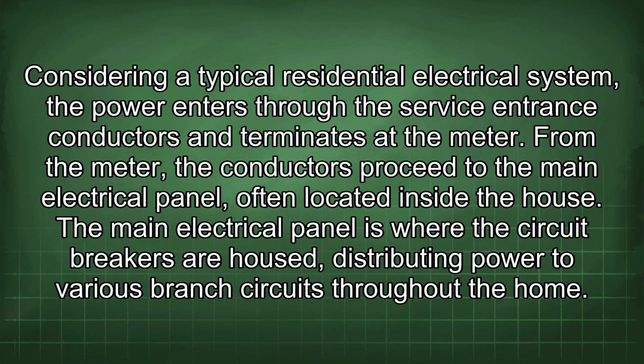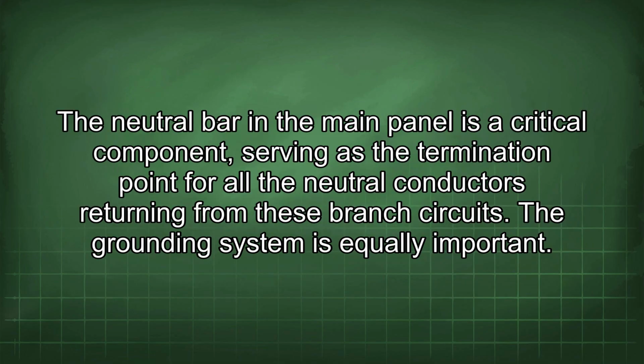Considering a typical residential electrical system, the power enters through the service entrance conductors and terminates at the meter. From the meter, the conductors proceed to the main electrical panel, often located inside the house. The main electrical panel is where the circuit breakers are housed, distributing power to various branch circuits throughout the home. The neutral bar in the main panel is a critical component, serving as the termination point for all the neutral conductors returning from these branch circuits.